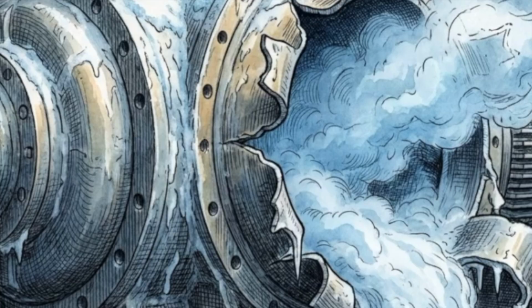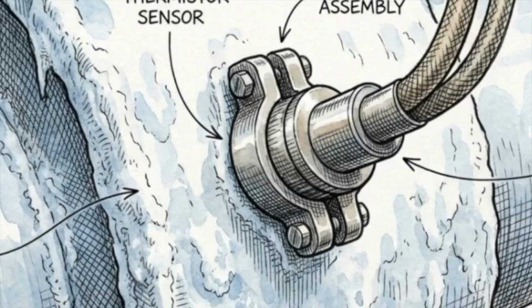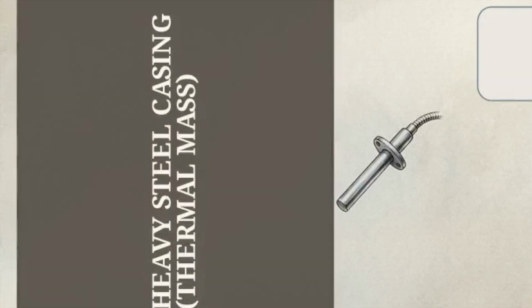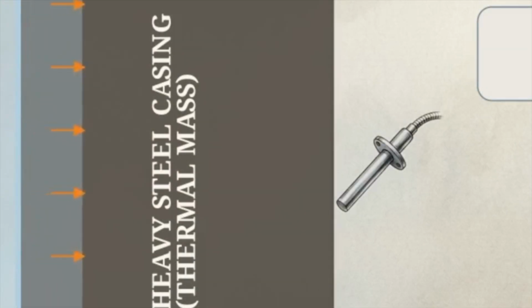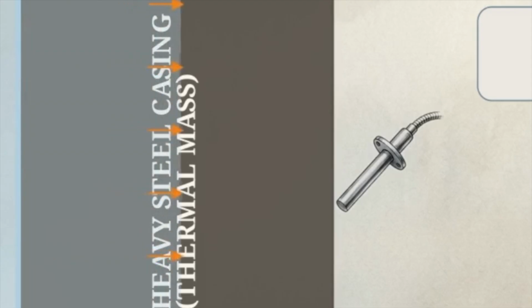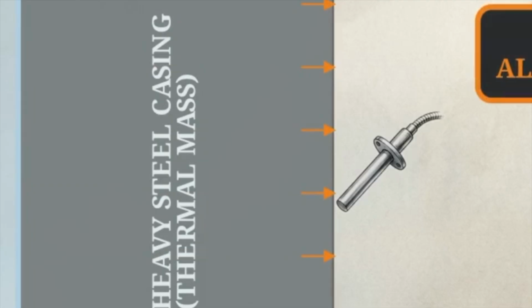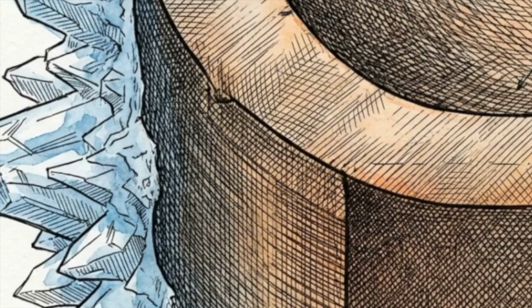Industrial cooling failure rarely looks like a gradual mechanical decline. It is a sudden, violent hydraulic explosion that destroys the hardware and immediately halts production. To prevent this, the industry relies on an external safeguard, a temperature sensor, or thermistor, mounted directly to the outside of the compressor casing. These sensors operate under a severe physical constraint. They depend entirely on thermal conduction, meaning the cold anomaly has to physically transfer through heavy metal before registering a drop in temperature. The dense thermal mass of the steel casing acts as an insulator, creating a massive delay in the reading.